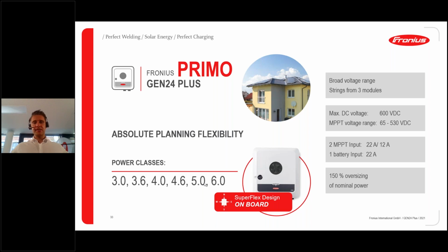For example, if you have got the Fronius Primo 3.0 GEN24 Plus, you can put up to 4.5 kilowatt peak on the PV generator side. That's the 150%.